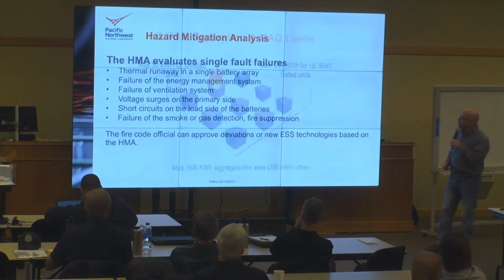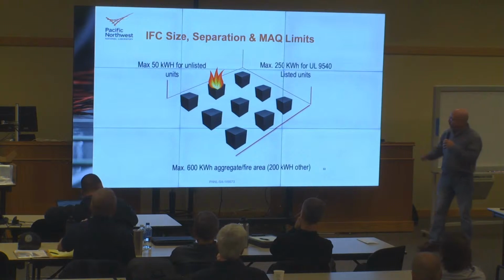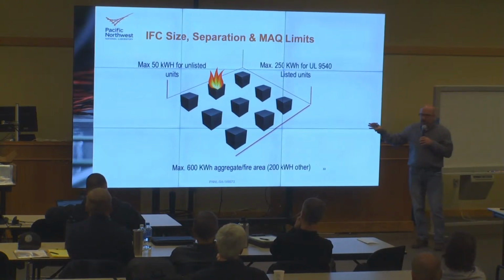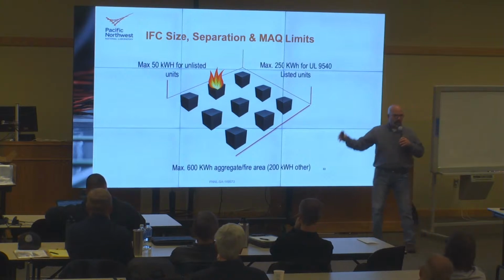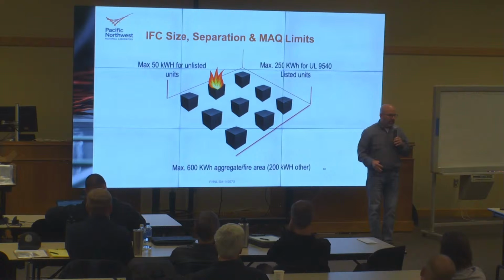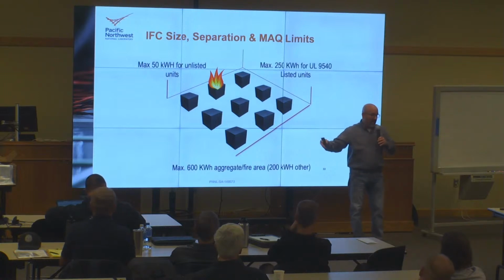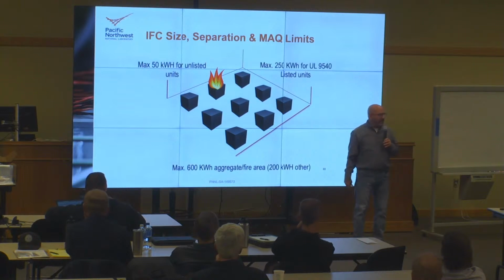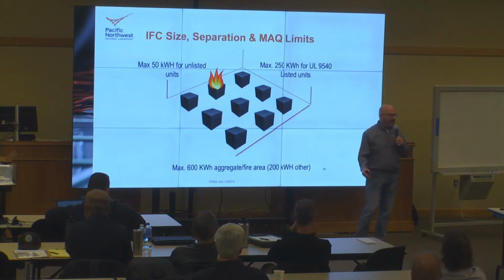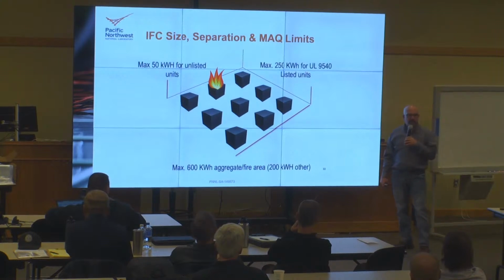So the whole 3-foot size and separation, when this was first introduced in the codes, that's what we said. We said you can't be larger than 50 kilowatt hours or closer than 3 feet apart without doing a fire test to tell us that it's safer. And the industry said, where'd you pull that 3 feet out of? We said, exactly, tell us a better number because we don't have the data yet. So it was absolutely an arbitrary number, but you have to start somewhere.